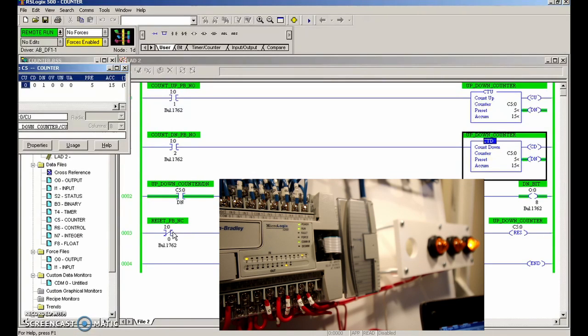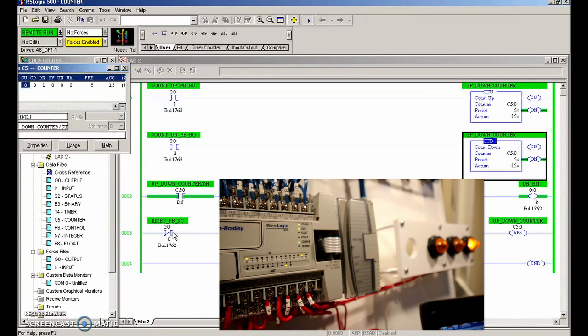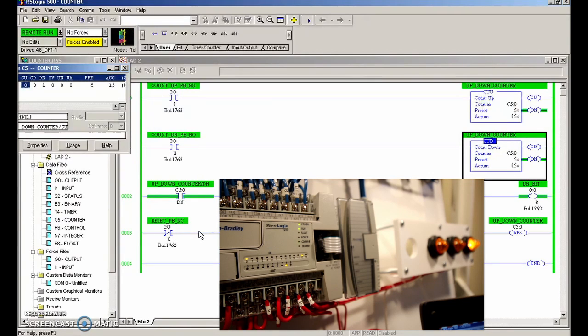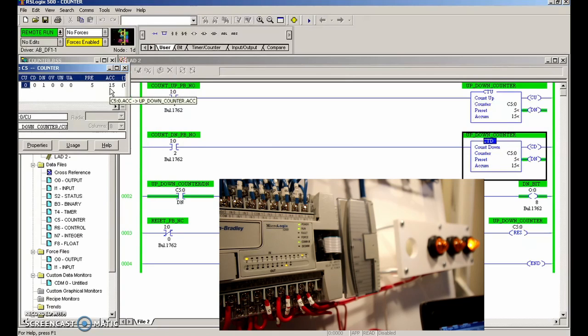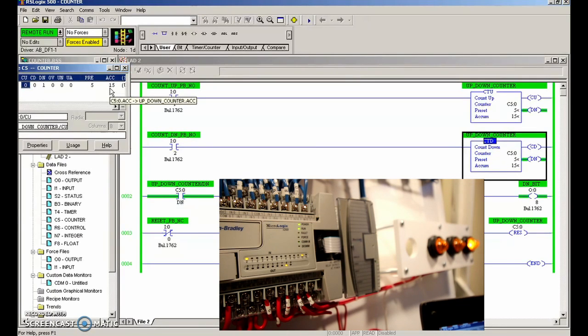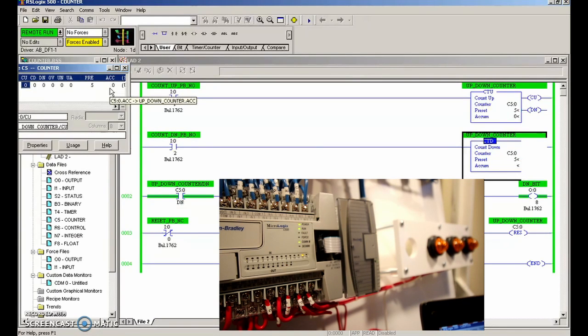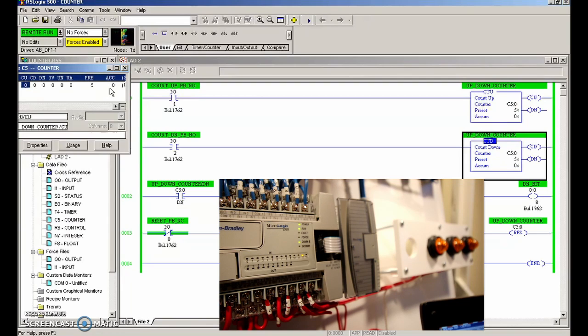I'm examining when it is no longer true, or when that light goes out, or when there's no longer any voltage. When I press that push button, I will stop that 24 volts going to that input, and that will make this rung true and reset my counter. So now I've got an accumulated value of 15. When I hit that reset button in three, two, one—you can see that accumulated value goes down to zero. I'm going to let go of that guy and it remains at zero. Beautiful.